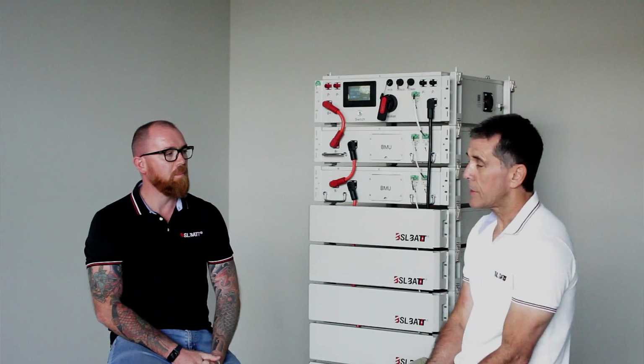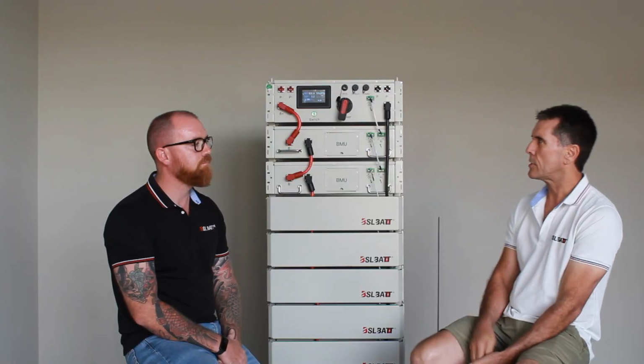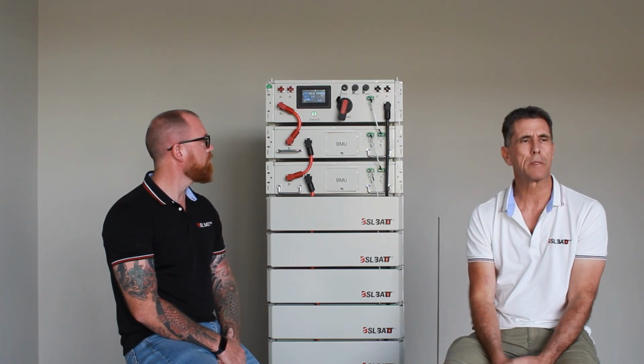Andre, tell us more about this battery. This is very exciting - as an ex-installer, we know where the problems are in terms of installing a battery like this. It wasn't designed by myself, it's actually designed by Scott. The whole idea behind this topology is that you can choose the nominal volt you require, from anything up from 150 volts right up to 950 volts, so we can cater for all inverters. As you can see, it's stacked 10 high with the BCU on top, which is basically the master BMS.